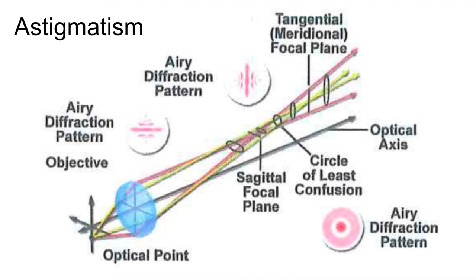So what can cause this? This can be from asymmetry in the lens. So again, sort of a manufacturer design issue with the lens, or it can also be how it's been mounted in the barrel. So if you're familiar with the objective lenses in your microscope, you'll know that the lens is actually mounted into a metal barrel. And so if there's incorrect mounting there, then this could also cause astigmatism.